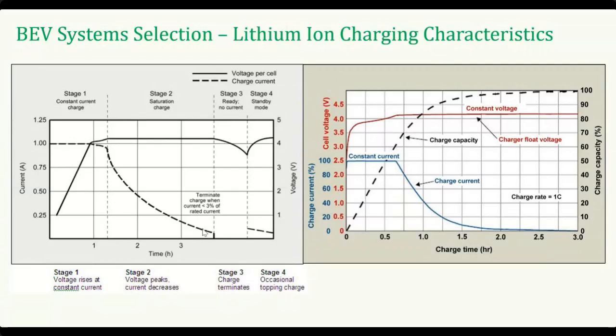With higher current, the stage 1 duration can be greatly reduced, but stage 2 will still take longer because the current must decrease from a higher value down to 3 to 5% for the battery to reach its potential voltage.